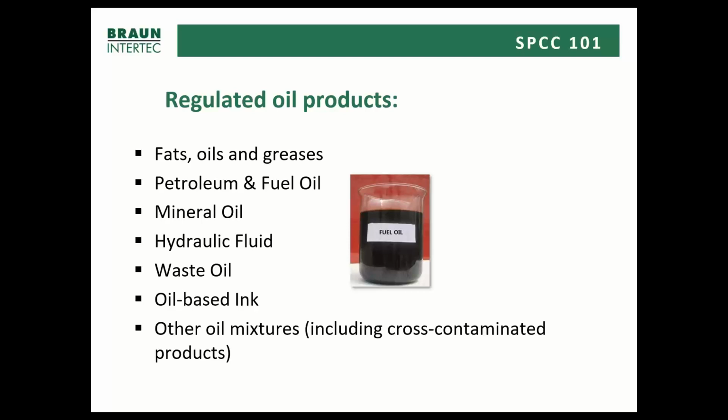waste oils, so used oils. There's a lot of inks that are oil-based, whether they're based in linseed oil or a petroleum oil. It doesn't matter, it's still regulated by the SPCC rules. And then we have other oil mixtures, including products that may have started off when they were new as not containing oil, but because of some use, and I'm thinking antifreeze, exposure to perhaps cracks in a crankcase, may have become cross-contaminated and have oil as a result of being used. Those are also regulated under the federal SPCC rule.